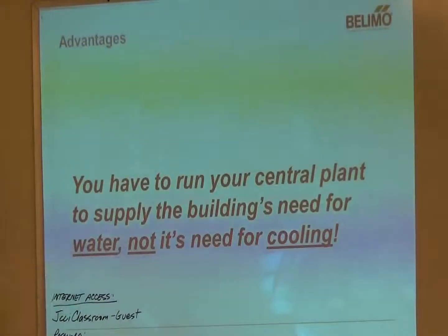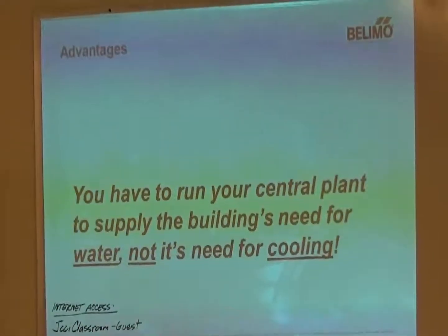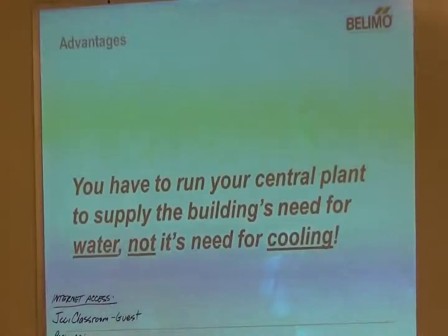So what we're saying there is that you have to run your central plant to supply the building's need for water, not its need for cooling. And what we're getting at is that you're bringing on this additional chiller not because of anything that's required from the load, just because of the additional flow that's being pushed around the building.